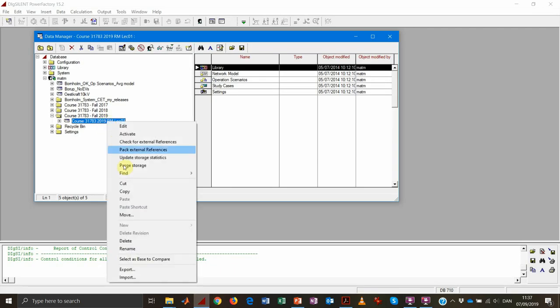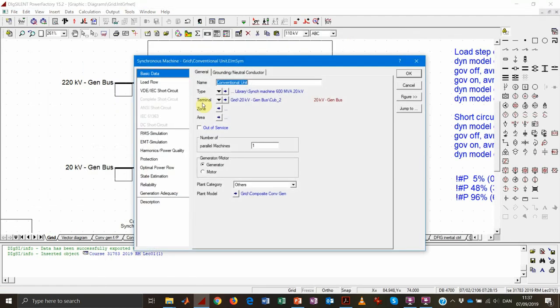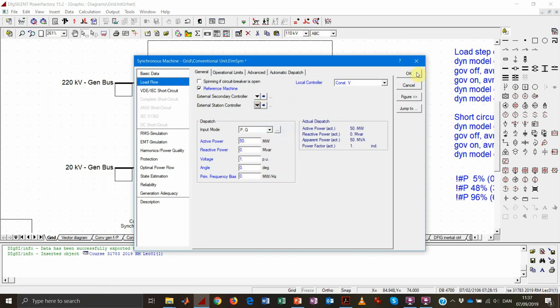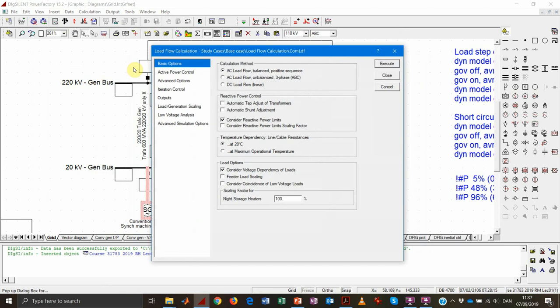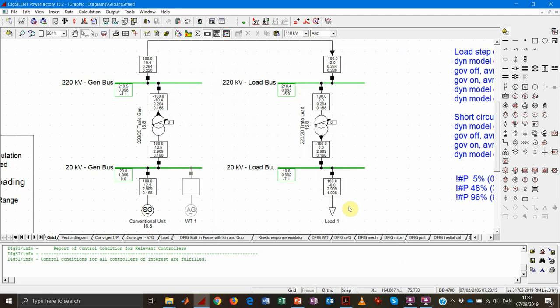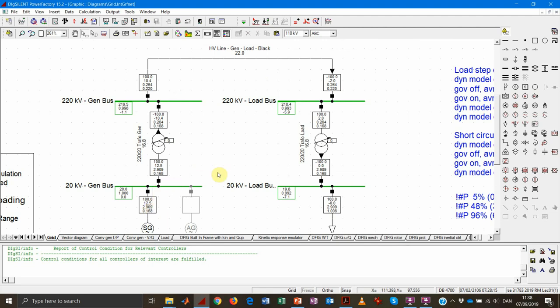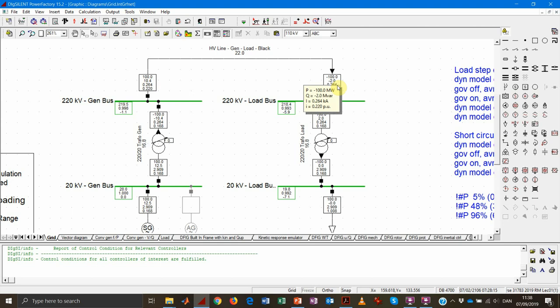Let's go into PowerFactory and make a copy of our radial grid. Let's remove the station control so we can have the voltage set at the generator bus, and also remove the reference bus so our reference bus will be on the generator instead of the load as before. Let's run the load flow at 100 megawatt. Right now the line has no resistance so it does not lose any active power, but it has a reactance so it is consuming some inductive power, as you can see from the active and reactive power flow at each junction of the line.